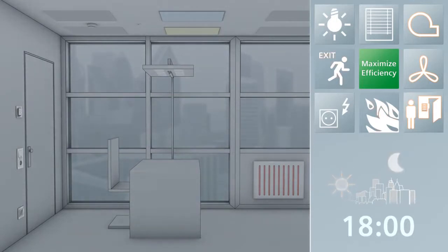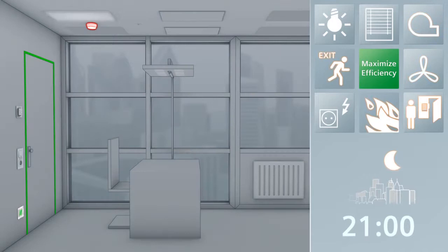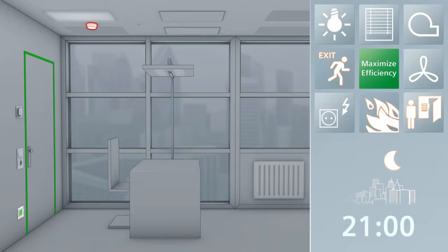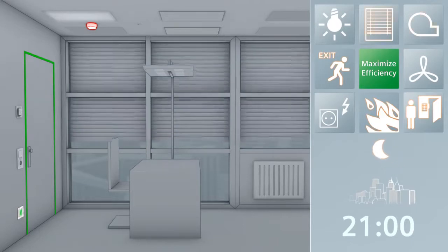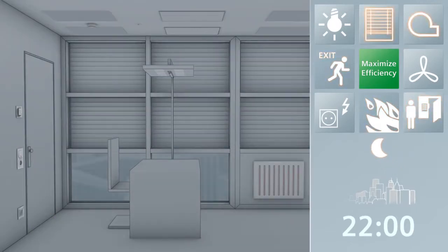In the event of a fire alarm, emergency lighting is activated so that people may safely evacuate the building. At the same time, all door locking systems are opened and the ventilation, heating and air conditioning are deactivated. After the alarm is over, nighttime mode is reactivated for the building.